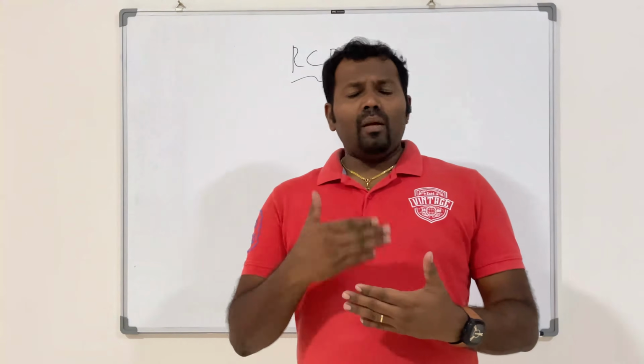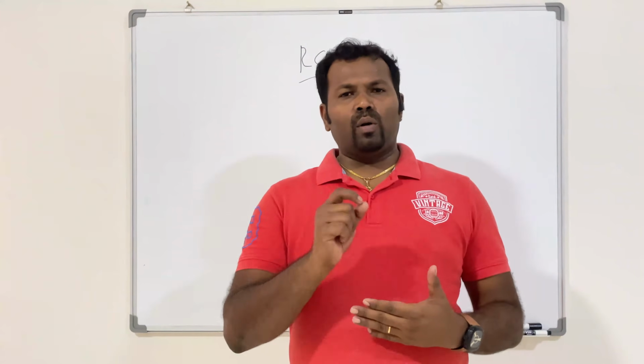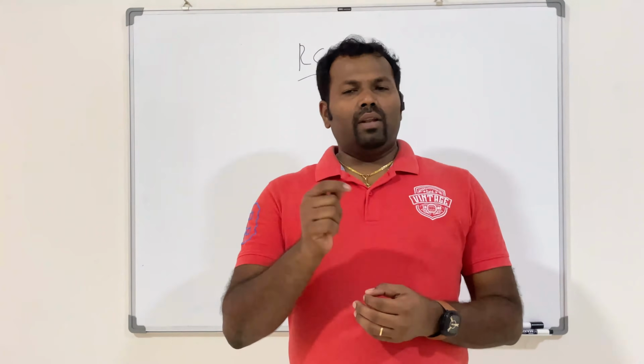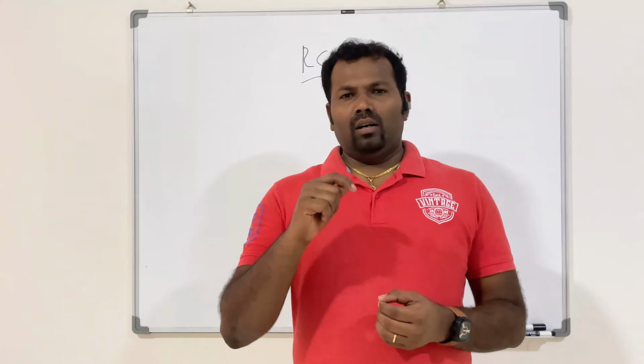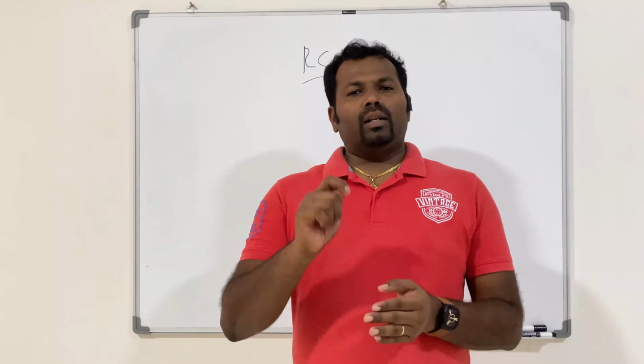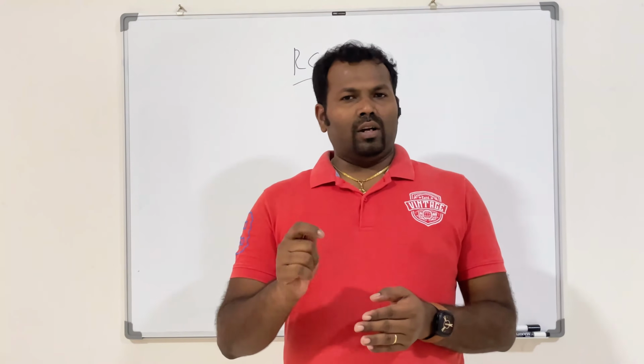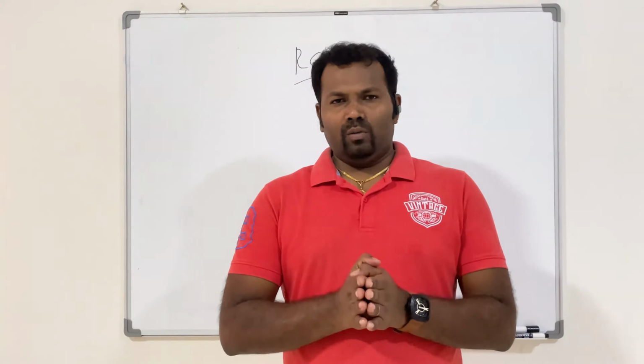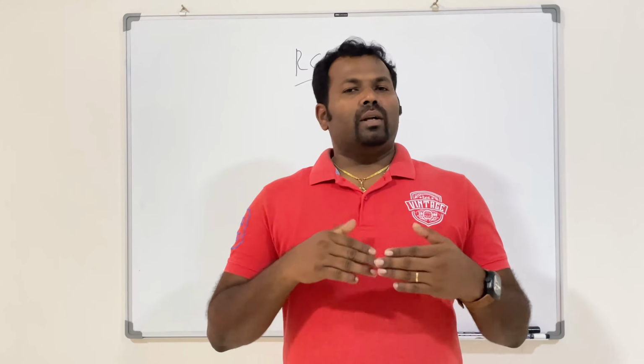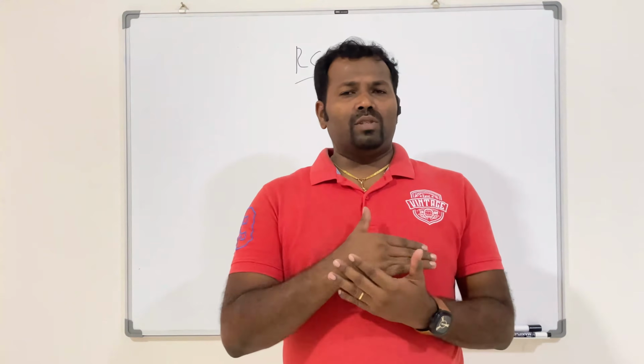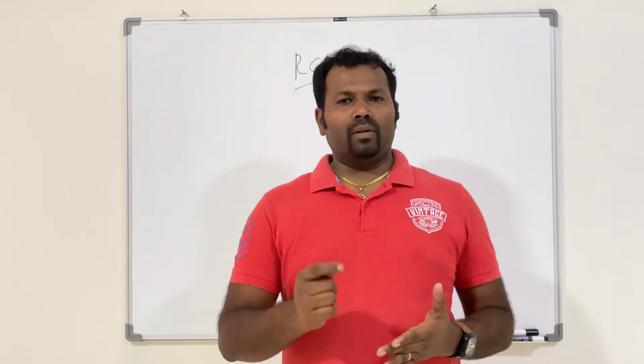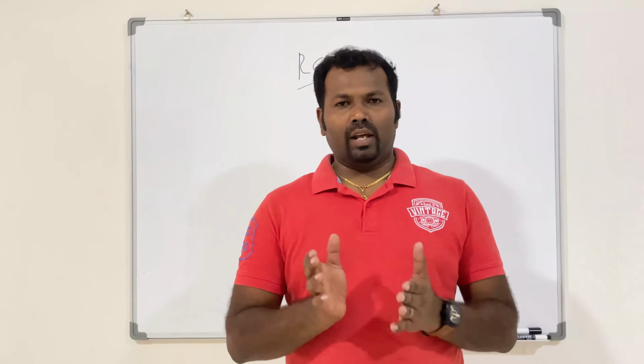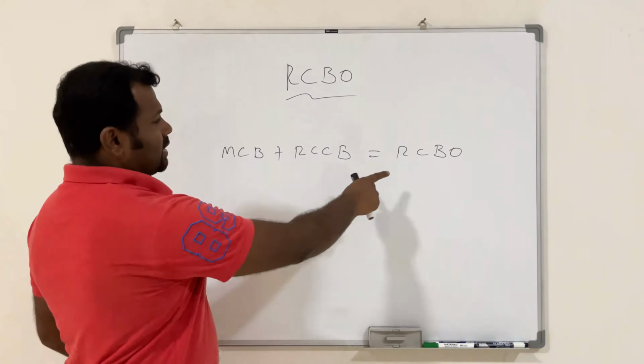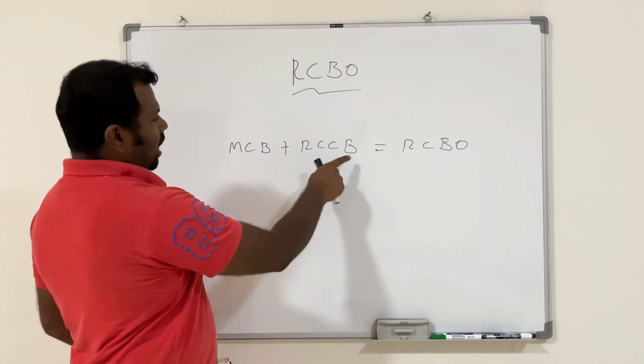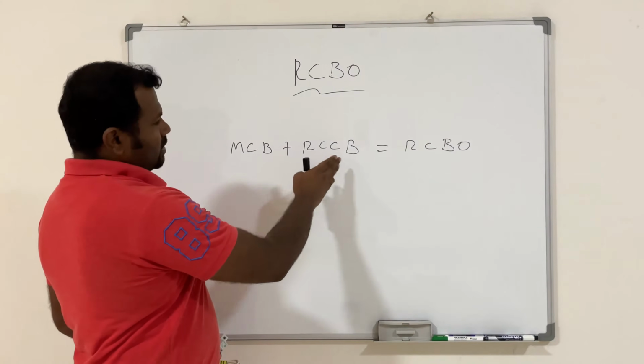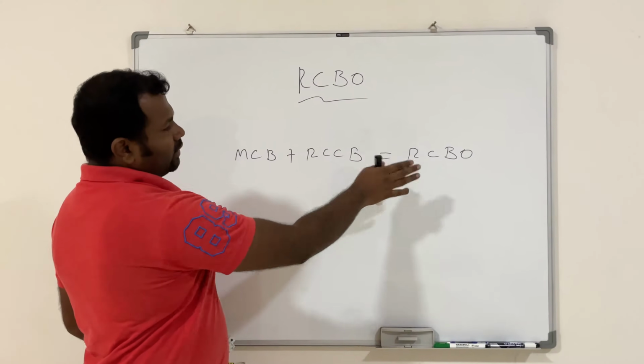Basically, MCB will protect us from overload and short circuit, but it will not protect from electric shock or leakage current. RCCB will protect us from electric shock or leakage current, but it will not protect from overload and short circuit. This RCBO is a combination of MCB and RCCB, so it will protect us from electric shock as well as overcurrent and short circuit current.